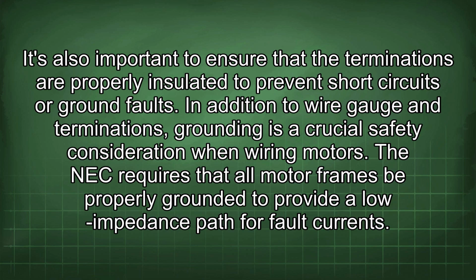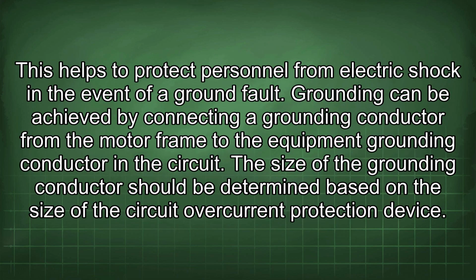In addition to wire gauge and terminations, grounding is a crucial safety consideration when wiring motors. The NEC requires that all motor frames be properly grounded to provide a low impedance path for fault currents. This helps to protect personnel from electric shock in the event of a ground fault. Grounding can be achieved by connecting a grounding conductor from the motor frame to the equipment grounding conductor in the circuit. The size of the grounding conductor should be determined based on the size of the circuit overcurrent protection device.